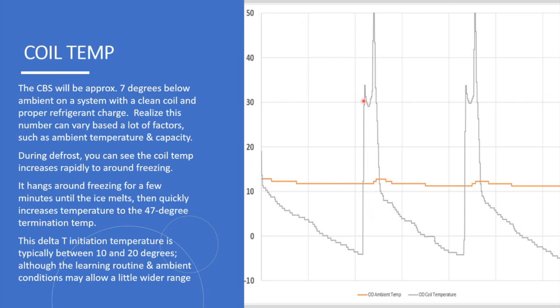At 32, it's going to stop there until it can melt the ice. All of the heat generated in the outdoor coil is going to go into melting that frost. So it won't go up in temperature until the frost is gone. You can see it kind of sticks at 32, and then it shoots up, and once it hits 47, it's going to terminate the defrost and then go out of the defrost cycle and start it all over again. When that coil starts to frost up, gets colder, it goes back into a defrost. And that's how it triggers it.